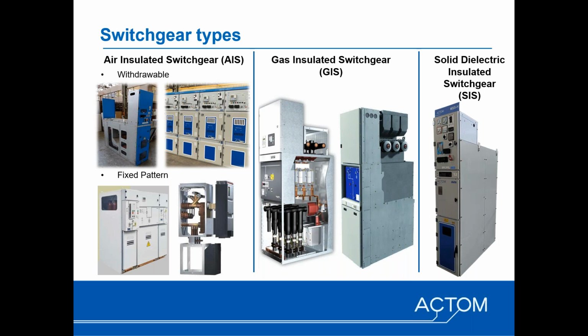The first four, so oil, air, SF6, and vacuum, are all regarded as mechanical switching devices. Then in terms of the assembly, just some examples here. On the left, we've got air-insulated switchgear. We didn't cover oil. It's less common these days. The main reason being that from a safety point of view, it's difficult to classify and test oil-filled switchgear. So we've excluded that from this particular slide.